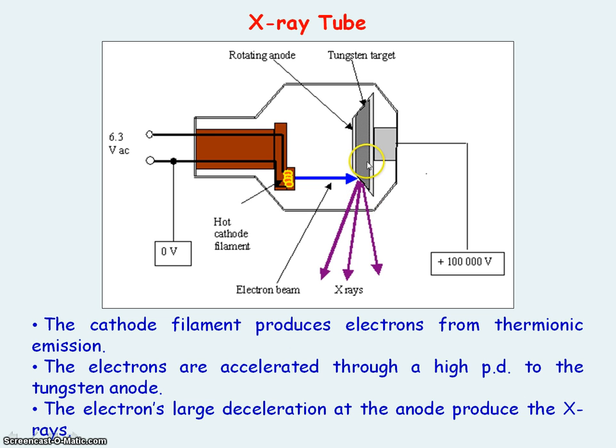Because a lot of heat is produced, the tungsten anode is rotated so that the area the electrons collide with constantly changes, thus allowing time for that area to cool down by radiating heat to its surroundings.